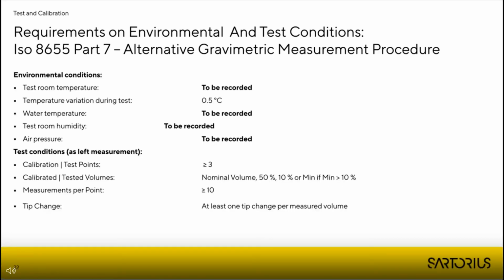If we compare the requirements of Part 6 to the requirements under Part 7, we see the following differences that are highlighted here. The test room and water temperature, as well as the humidity, now just need to be recorded during the calibration, but there are no limits given. Same as under Part 6, the temperature shall not vary more than 0.5 degrees from beginning to the end of the test. The requirements on test points, tested volumes, and measurements per test point are exactly the same as under Part 6.